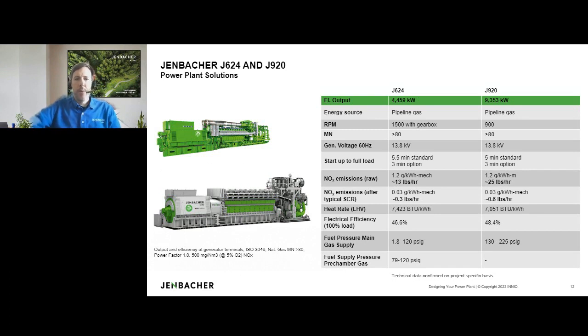Now going into a little more detail on those two engines I had mentioned, the 624 and also the 920. These are the two options really for utility style power plants, which we're promoting. The 624 is the 4.5 megawatt unit, which I had just talked about a bit here. It is running on typically pipeline natural gas, and the performance data we have here is based on methane number 80. All gas engines are always rated at a certain methane number, but obviously we also have fuel flexibility to go with lower methane numbers. This engine typically produces medium voltage power at 13.8. We also have other voltages as options.